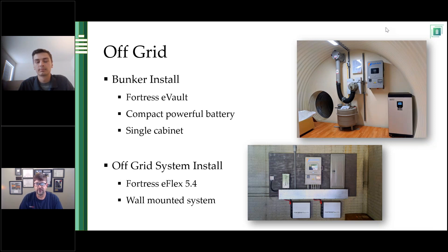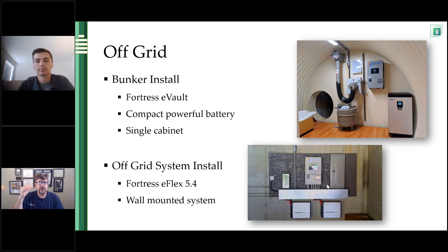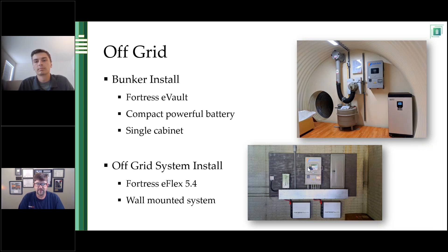We combine them in a wiring trough with a combiner bus bar inside where they're paralleled together. We make sure cable lengths are the same. The batteries are all connected together. Fortress has closed-loop communication with Sol-Ark — a green dialog box pops up and you can run the battery at a slightly higher voltage, getting better warranty performance and battery life when everything's working together. Both the e-Flex and e-Vault are totally different-looking installations but the same battery chemistry — they perform the same kilowatt to kilowatt. I typically undersize — two batteries in there — but you can. Next slide is time of use.